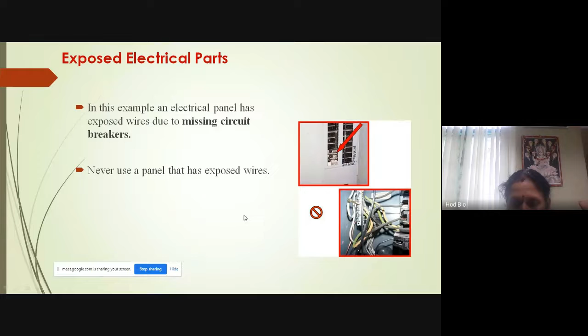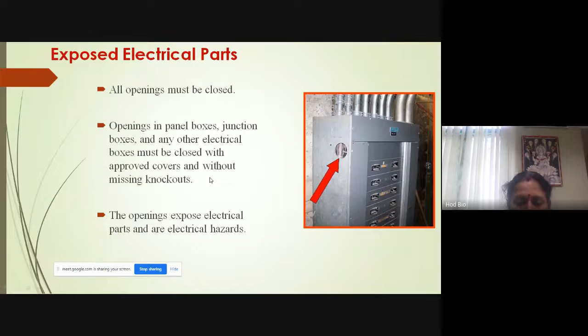Any open holes, you need to close immediately, otherwise they create electrical hazards. Openings in the panel box, junction box, and any other electrical box must be closed immediately and covered, without missing knockouts. Now, outer insulation. You see here in this figure, the outer insulation is removed. There's some gap there.